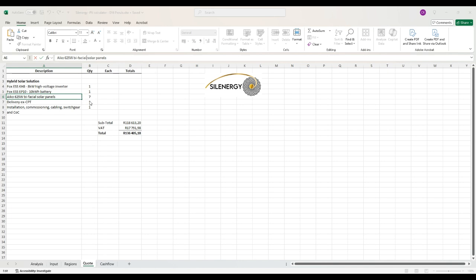The battery, again, is about not only the backup facility, it's also about doing what we call peak shaving. That's the practice of making solar power during the day, charging up the battery, and then saying you're allowed to use maybe 50% of the battery in the evening, between roughly 4 o'clock and 8 o'clock, or as long as the battery lasts, down to 50%. The other 50% is reserved for backup.